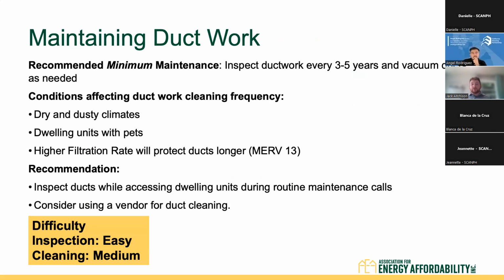So maintaining ductwork. Recommended minimum maintenance is to inspect ductwork every 3 to 5 years and vacuum as needed. Very similar to air filters. Conditions affecting ductwork cleaning frequency are dry and dusty climates and dwelling units with pets. Higher filtration rate will protect ducts longer. So if you have better filtration, there's going to be less gunk in your ducts, and you're going to be less frequently required to vacuum out those ducts. And then recommendation, inspect ducts while accessing dwelling units during routine maintenance calls, similar to the air filter. And then consider using a vendor for duct cleaning.